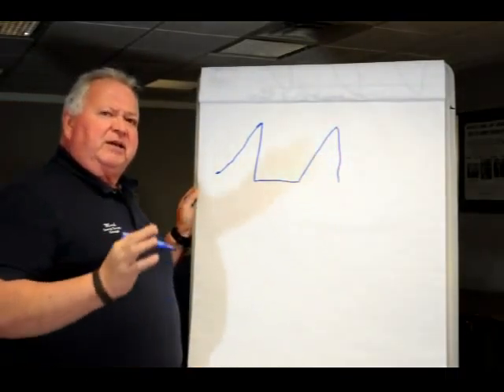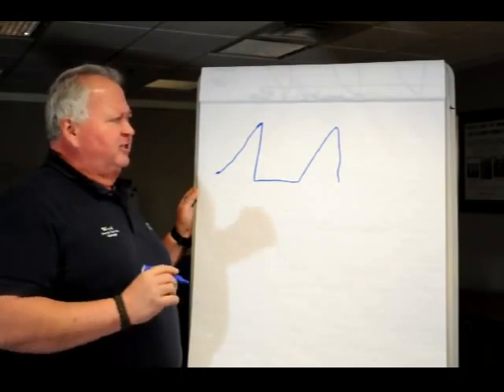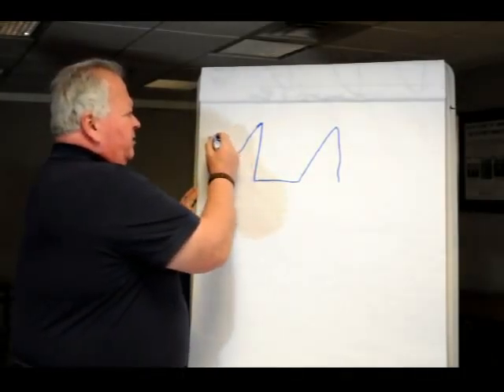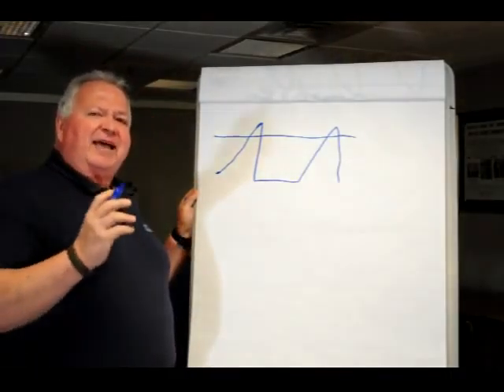If you look at when this piece of appliance actually achieves its efficiency and you draw a line across those peaks, it's only at that steady state or AFUE rated efficiency, roughly 8% to 10% of the time it's in operation.